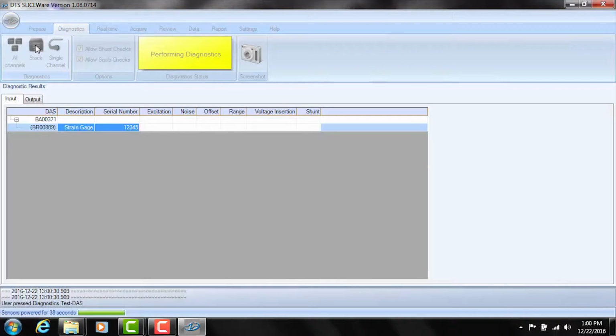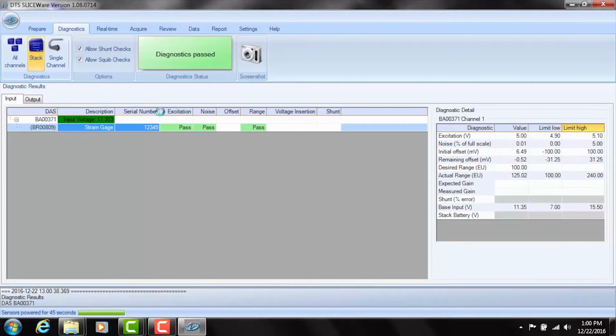I'm going to press the stack icon. You can see now it's performing diagnostics, doing various checks, like checking excitation voltage, noise, offset and range, and so on, depending on the sensor type. So we finished the diagnostics now, and green is always good. If you pass the diagnostics test, there should be green highlighted areas that say pass. If there was any kind of failure, you'd see a red block denoting the failure. If you wanted to understand specifically what failed, on the right side here is a table, and you can see the diagnostics values that were measured against the upper and lower acceptable tolerances. Okay, so we passed the diagnostics routine.